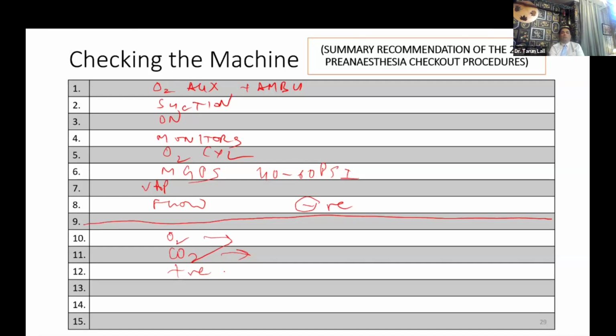These days, you are not doing these tests also because most of these tests are automated. So all these tests regarding the circuit, which I have just told you, the pressurizing, the negative pressure, are already done by the machine. But what you will have to do is all these other tests which the machine is not doing. So suppose you have a GE station. You know that these are the tests that the machine has already done. But obviously the machine has not checked whether the vaporizer is full or not, whether your CO2 absorber is exhausted or not. So those tests you will have to do.